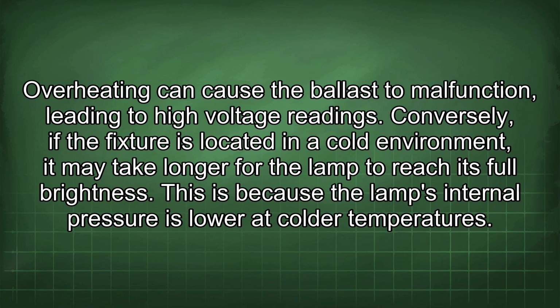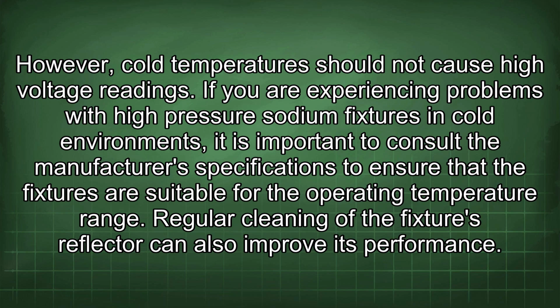Conversely, if the fixture is located in a cold environment, it may take longer for the lamp to reach its full brightness. This is because the lamp's internal pressure is lower at colder temperatures. However, cold temperatures should not cause high voltage readings. If you are experiencing problems with high-pressure sodium fixtures in cold environments, it is important to consult the manufacturer's specifications to ensure that the fixtures are suitable for the operating temperature range.